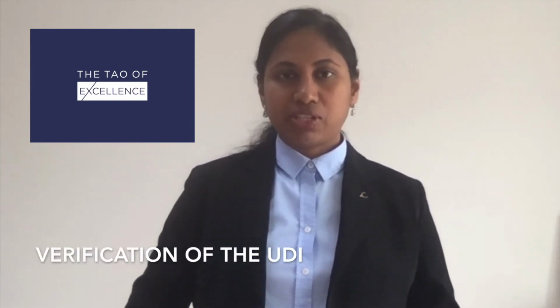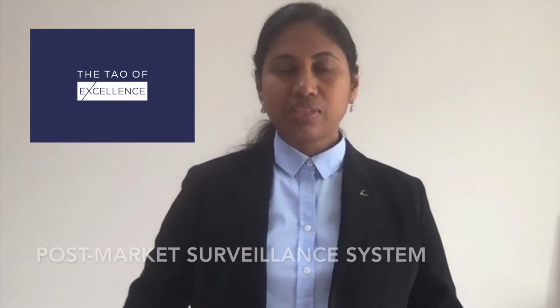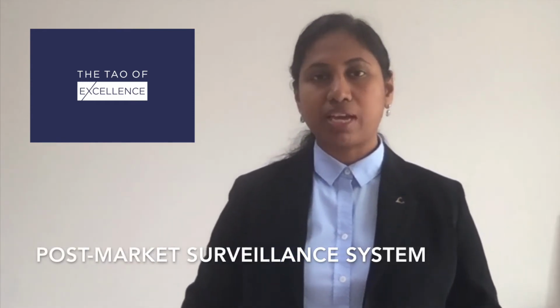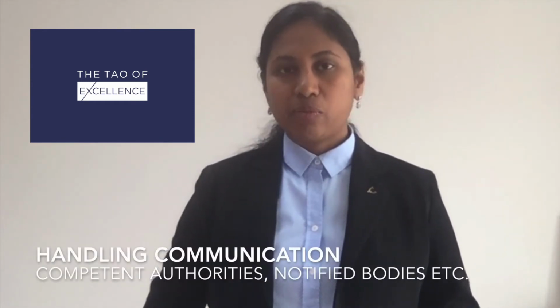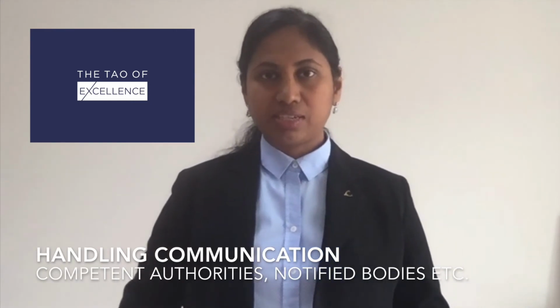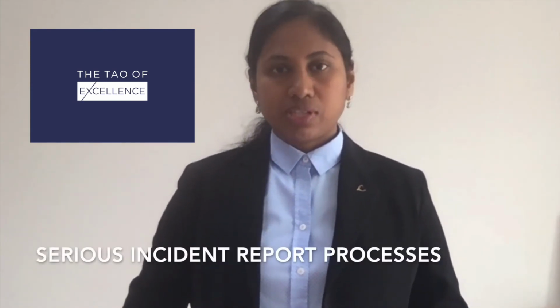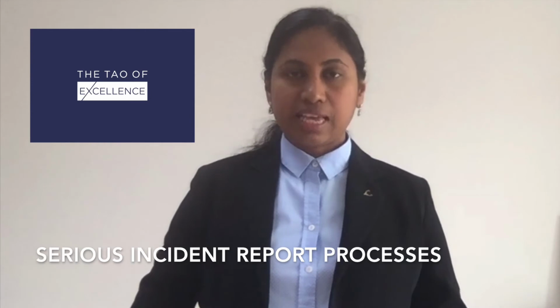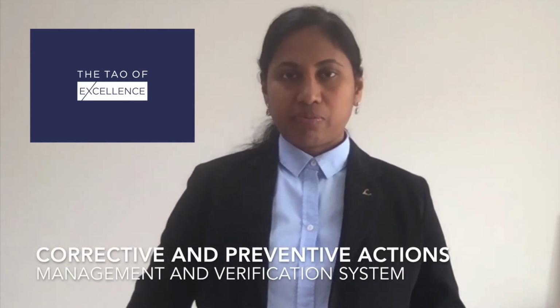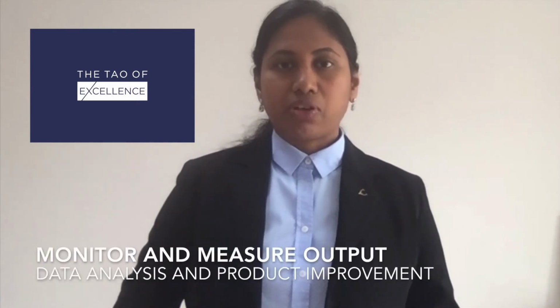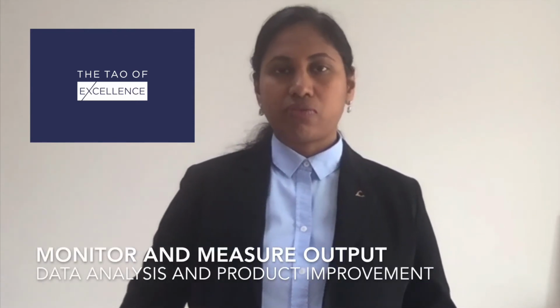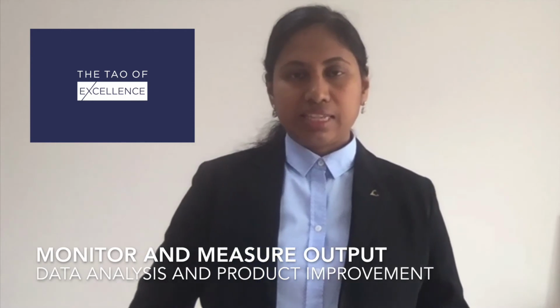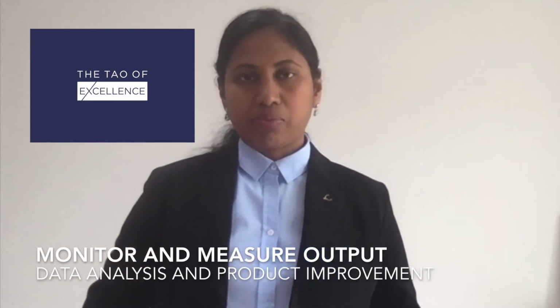verification of the assignment of the UDI, setting up and maintenance of the post-market surveillance system, handling communications with the competent authorities, the notified bodies, other economic operators, the customers and other stakeholders, process for reporting of serious incidents and field safety corrective actions, management of the corrective and preventive actions, and process for monitoring and measurement of output, data analysis, and improvement of the product.